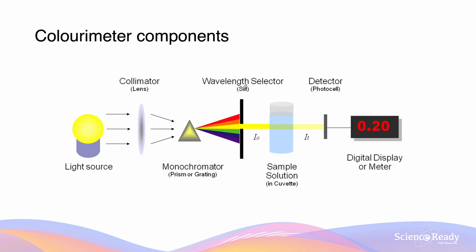Let's look at the components of a colorimeter. In our colorimeter, we have a light source, which is then focused by a collimator — that's just the lens — and that light source is then refracted through the monochromator and passed through a wavelength selector. This wavelength selector is going to filter out our undesirable wavelengths of light which we do not want to analyze. Once this is done, that wavelength of light passes through our sample of solution, and a detector will then determine how much of the light was absorbed and display that on a digital display.